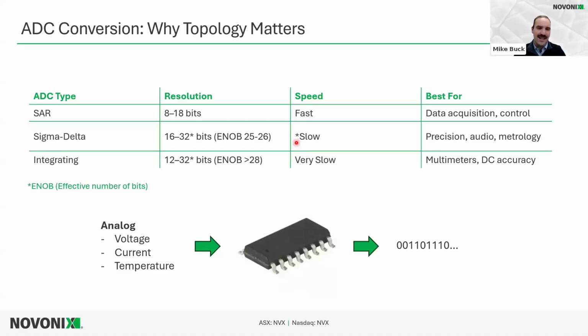But in order to really achieve the full metric of bits, you have to go through a very deep stage of analysis on your analog to digital converter, and there has to be supporting circuitry around it to achieve it. Just because it states a number doesn't mean the instrument will actually achieve that. That's part of the challenge with designing a high precision measurement instrument.